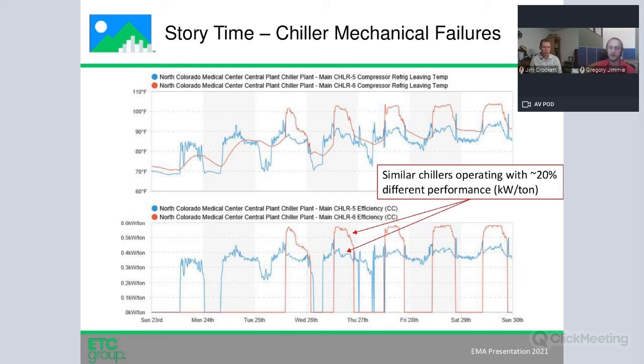We started to manually manipulate the way these chillers were operating. We first kind of tried to level the playing field. We equalized flow. We did everything in our power to make sure that they were as close to the same capacity or load as one another. And even in doing that, we still were seeing the compressor consume more power on chiller 6.